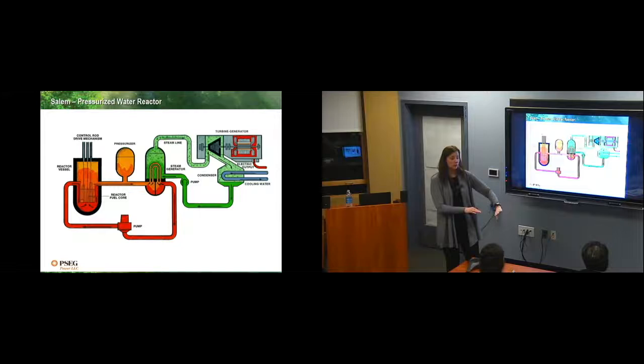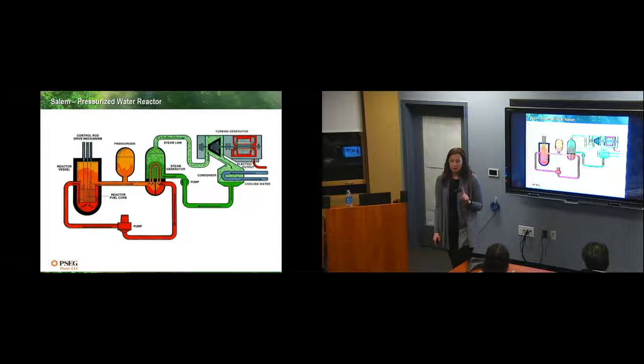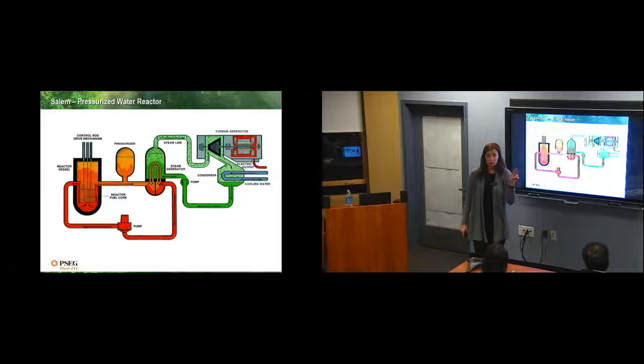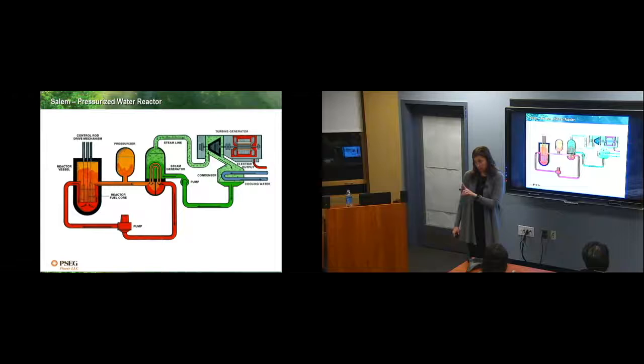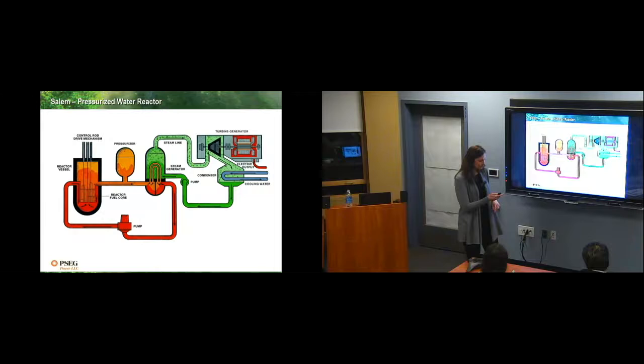Now, the steam, we need that to travel back around because we want to use the same water here. But the steam won't travel back efficiently. So we need to condense it. So we heated the water up to turn it into steam. So we cool the steam down to turn it into water, to come back around to turn back into steam. So these are the units, one and two, that do not have the cooling tower. So this water is coming right from the Delaware River. 1.1 million gallons of water is coming through those pipes every minute. 1% of the river flow.